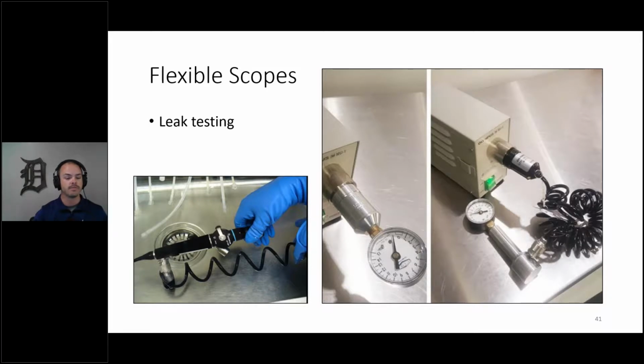The next critical step is that leak test we talked about earlier. Both Jahan and Seth touched on this, but what can we do with our leak tester? Often we get a leak tester and just have blind faith that it's always working. The IFU, admittedly, doesn't really help us much because it tells us to turn it on, push the pin, and listen for a whoosh. This isn't a very good process.